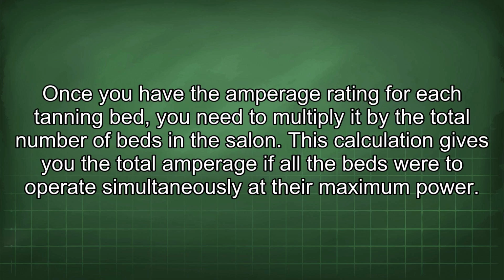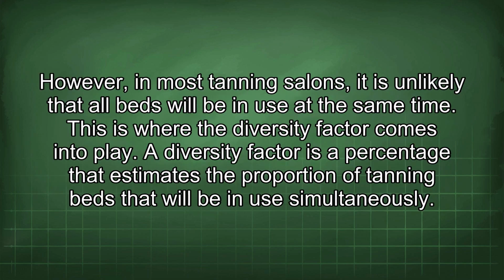Once you have the amperage rating for each tanning bed, you need to multiply it by the total number of beds in the salon. This calculation gives you the total amperage if all the beds were to operate simultaneously at their maximum power. However, in most tanning salons, it is unlikely that all beds will be in use at the same time. This is where the diversity factor comes into play.